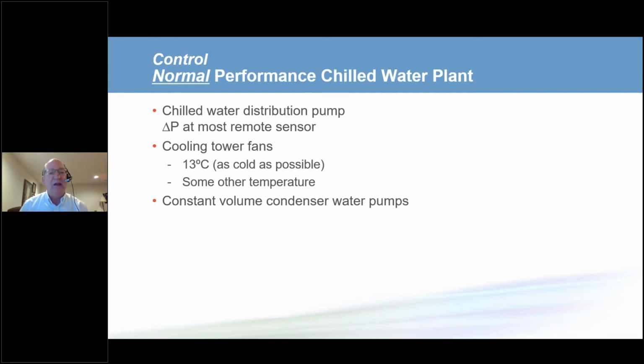As the valves change, the pressure changes, and we modulate the pump speed to maintain the pressure at that most distant coil. The cooling tower fans are often controlled to make the coldest tower water temperature possible. Now, in a climate like yours, where the wet bulbs are high all the time, that isn't as low as in a climate like mine. I'm in Wisconsin. Our wet bulbs are much lower than your wet bulb temperatures, particularly when it's not during the summer.